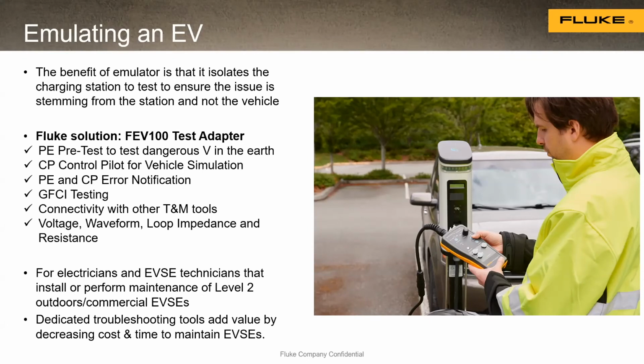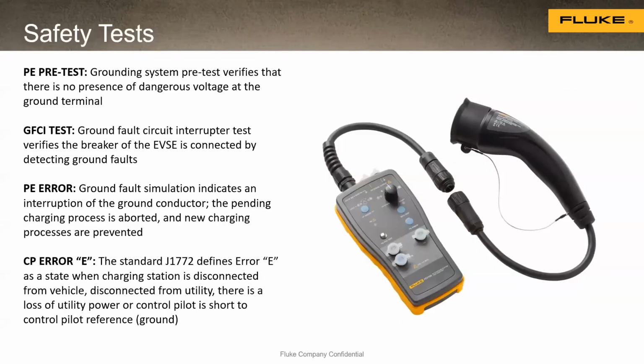This adapter does need to be hooked up to a DMM or potentially a scope meter, but once connected, we can look at the voltage, the waveform of the voltage, and the sine wave coming out of it. We can do loop impedance testing and resistance testing on it. This is for electricians out there, especially with level twos and commercial applications, to go out and troubleshoot this type of system. It's built for outdoor use, for troubleshooting as well as operations and maintenance. You can do a certification now and validate that the charging station is working correctly.